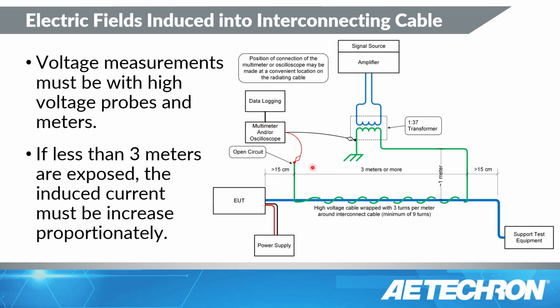If you use an oscilloscope, most oscilloscope probes are only rated for 300 volts. So if you do this measurement with an oscilloscope, make sure you're using a high voltage oscilloscope probe, usually the 100 to 1, some of them are rated to 1,000 volts. Some of the 1,000 to 1s are much higher voltage, and you may have to use something of that nature to make that measurement. Multimeters do have high voltage probes that can be used as well.